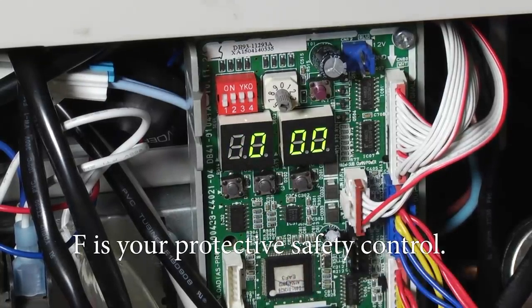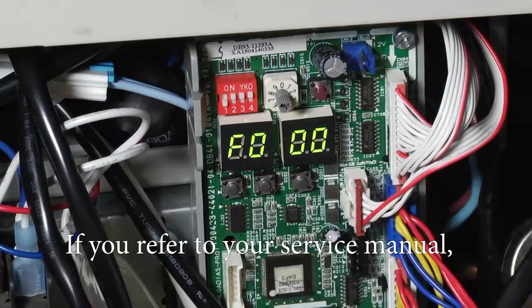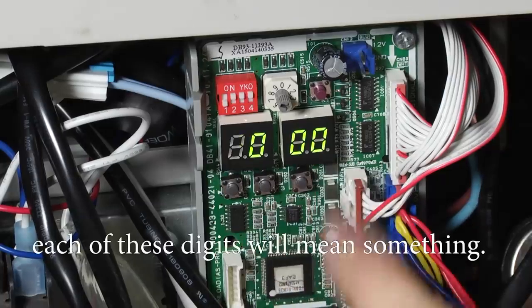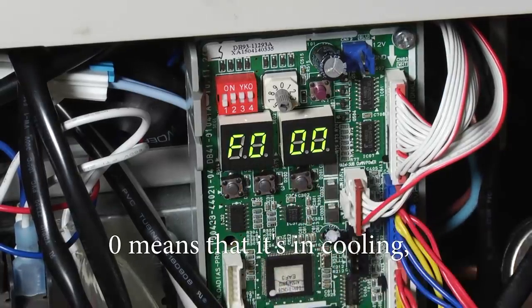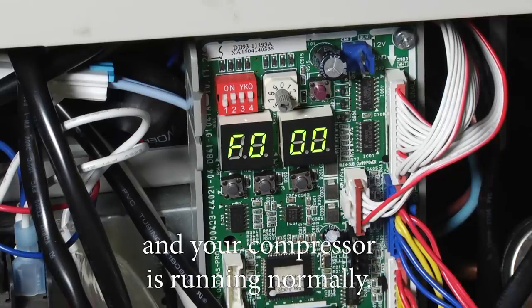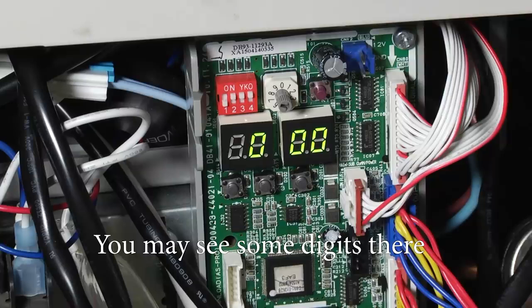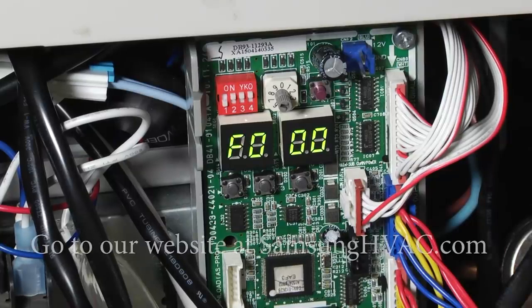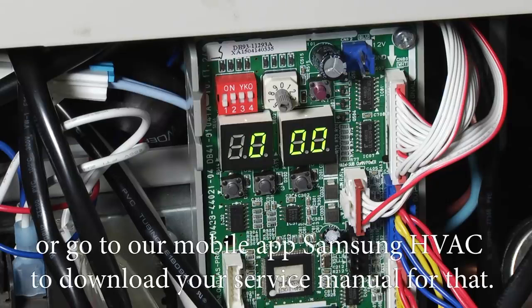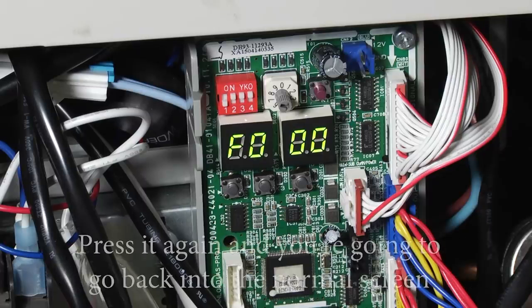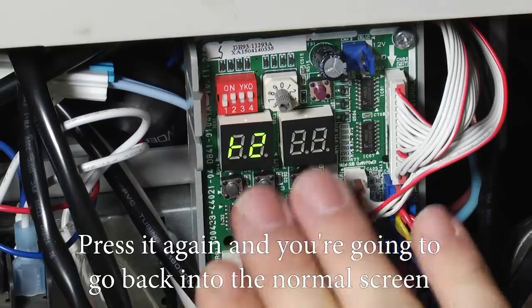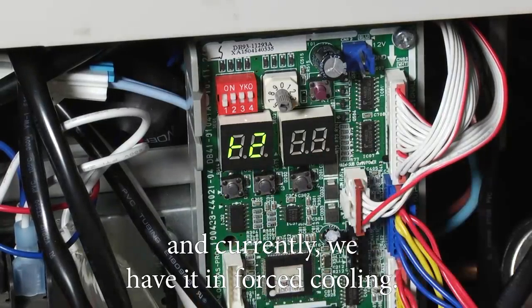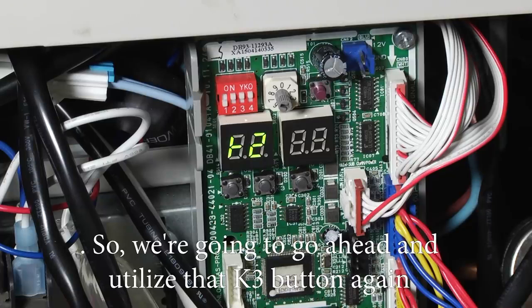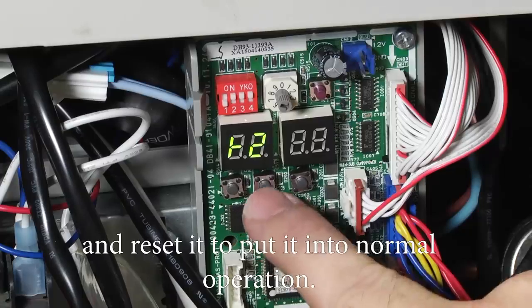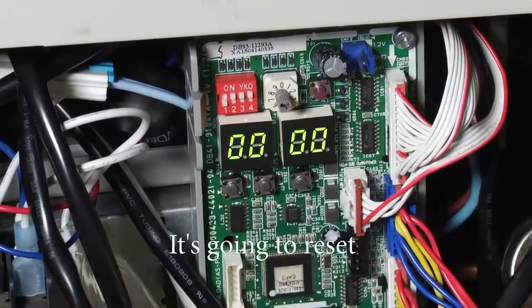We're going to push it one more time. And F is your protective safety control. If you refer to your service manual, each of these digits will mean something. 0 means it's in cooling, and 00 means there's no protective control and your compressor is running normal. You may see some digits there, but just refer to your service manual. Go to our website at samsunghvac.com or go to our mobile app, Samsung HVAC, to download your service manual for that. When you press it again, you're going to go back into the normal screen, and currently we have it in forced cooling. So we're going to go ahead and utilize that K3 button again and reset it to put it in normal operation.